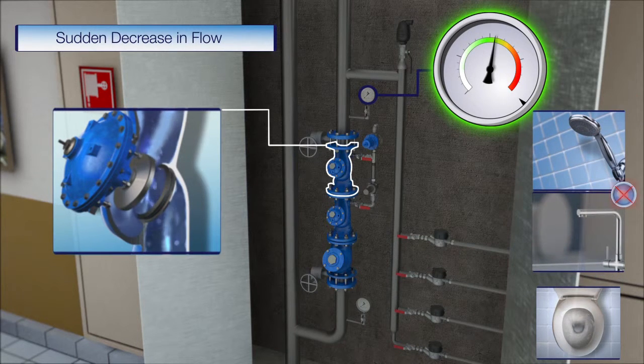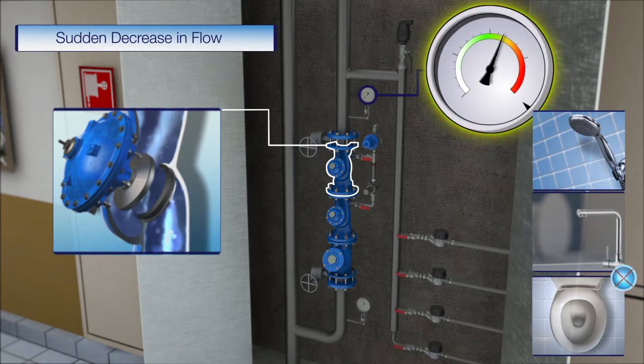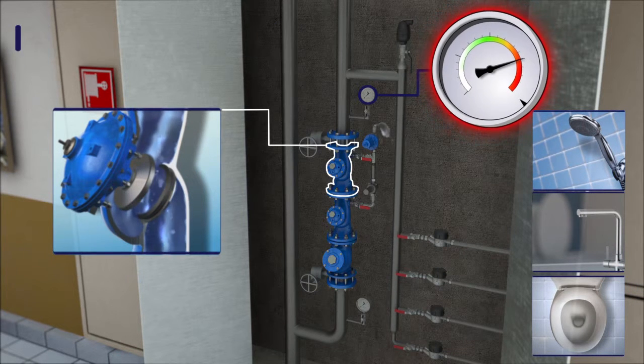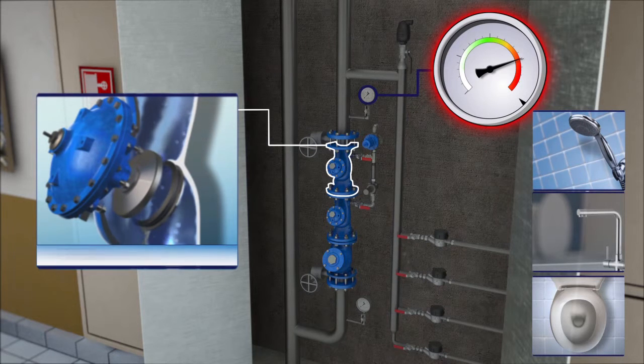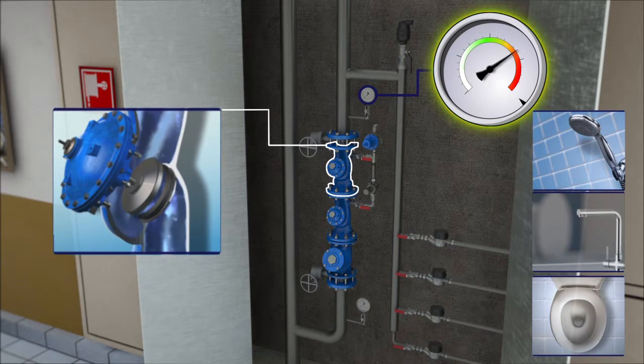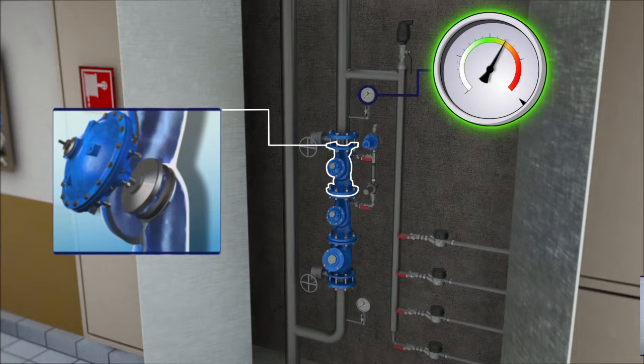When the demand for water suddenly drops, the downstream pressure rapidly rises beyond its safe setting. The emergency pressure relief valve opens its vent port for a short period, causing immediate reduction of the downstream pressure.